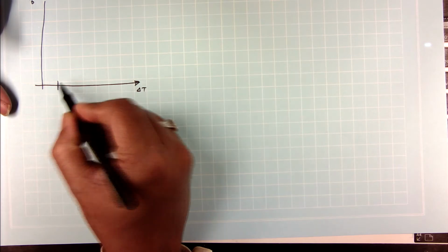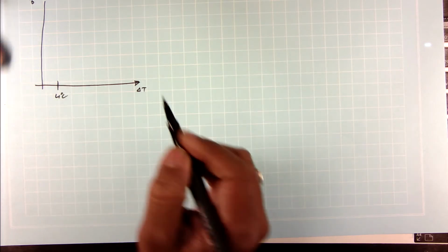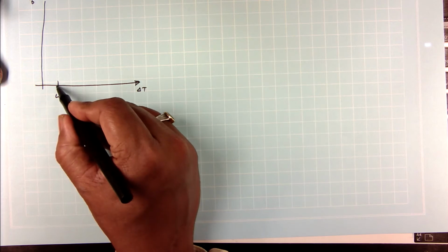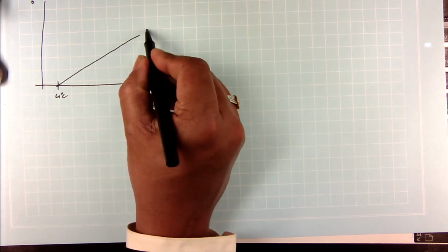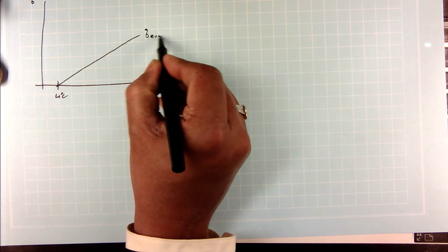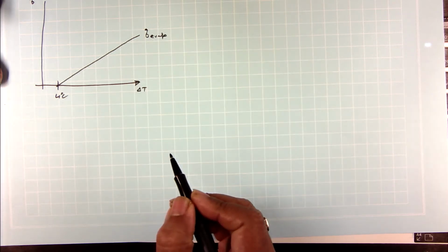In other words, the rate at which you can take vapor out of your system is the limiting factor here. Okay. So in other words, if as a function of delta T, I plot q double prime, the rate at which you are producing vapor, after about 4 degrees Celsius your vapor production starts, right? So the rate at which you can produce vapor is given by this line, right?